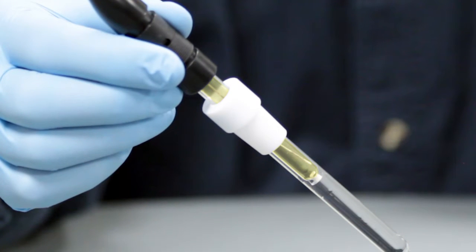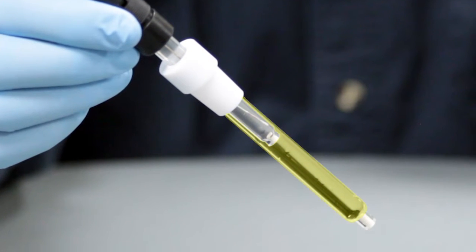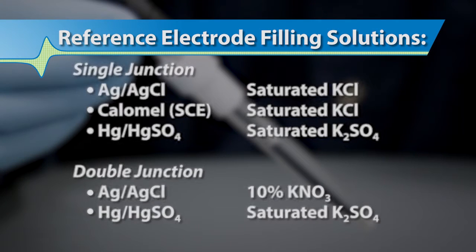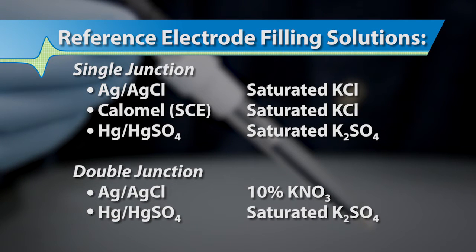The inner fill solution cannot be changed. The outer fill solution, however, can be changed. The appropriate filling solutions for your specific reference electrode are shown here.